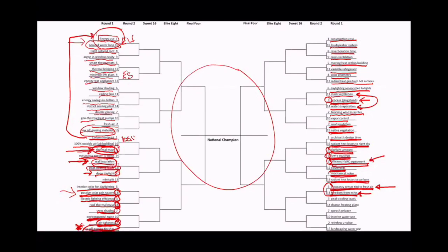Rounding out the rest of the West bracket, we have peak cooling loads. If you have a situation where we're making semiconductors and it can never get above 80 degrees, the peak cooling load is going to be very important. Otherwise, it's really not that important, especially if you talk to your client and say, look, we can save a ton of money and make the system way more efficient if you're willing to be uncomfortable for a couple of hours a year during the warmest part of the year. If it's a record-breaking day, just be okay being a little uncomfortable, put a few fans on your desks. We can save a boatload of money and a lot of room for mechanical equipment, save the planet, and make the system quieter—a bunch of good things come from that.